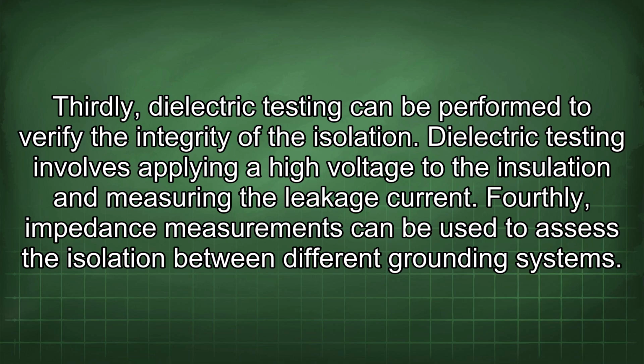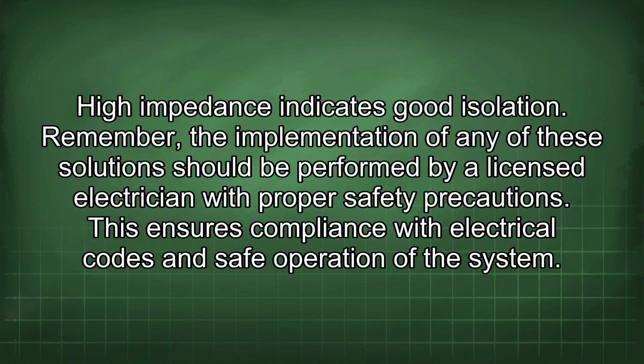Thirdly, dielectric testing can be performed to verify the integrity of the isolation. Dielectric testing involves applying a high voltage to the insulation and measuring the leakage current. Fourthly, impedance measurements can be used to assess the isolation between different grounding systems. High impedance indicates good isolation. Remember, the implementation of any of these solutions should be performed by a licensed electrician with proper safety precautions. This ensures compliance with electrical codes and safe operation of the system.